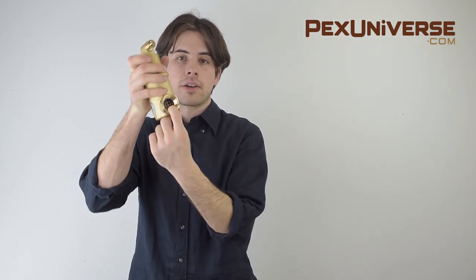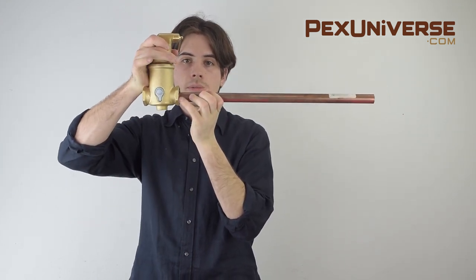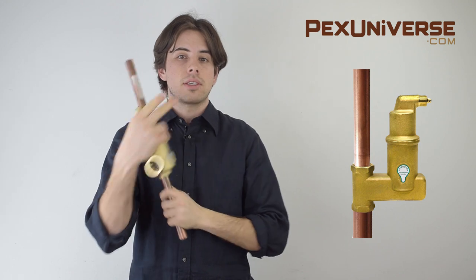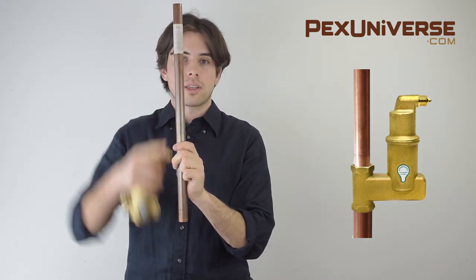Air eliminators and air separators can come with the connection options of sweat, threaded, and pressed connections. This here is a threaded connection as you can see by the inner grooves and most air eliminators are installed horizontally like this where the pipe just goes in simply like that. But as you can see here there are air eliminators that are installed vertically where the pipe runs like this.